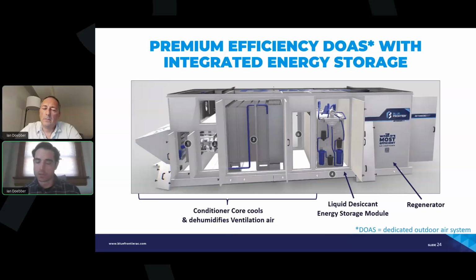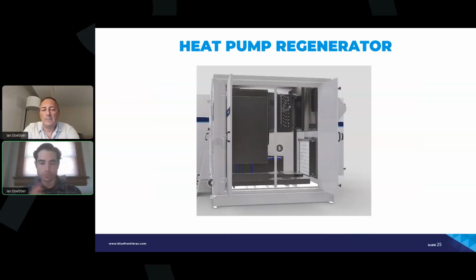The final subcomponent of the system is the regenerator, all the way on the right. I'll jump to the next slide for a more zoomed-in view. This shifts the perspective from the viewer to the end of the unit, looking into the regenerator. Essentially, this is a heat pump running in heating mode during the cooling season, a little bit non-intuitive, and we're pushing moisture out of the desiccant. In other words, the desiccant grabbed water from the air to provide the cooling going into the building. Now the desiccant is diluted, so we need to push the moisture out.